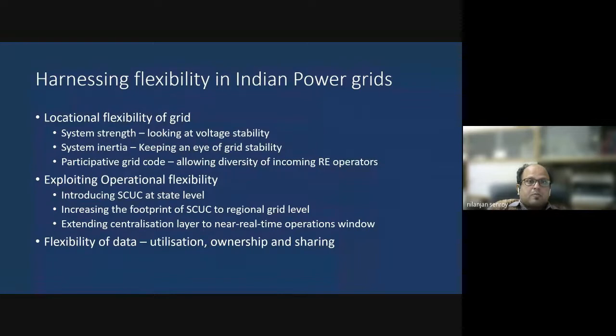Then at important nodes, we need to specify the minimum fault current levels that the grid will provide. And the fault current levels over the years at these nodes must be monitored. And if you find that the fault current levels are going down, then you need to install some equipment there in order to restore the fault current levels back to acceptable levels. So for instance, one very key source of fault current is the synchronous condenser that can help restore fault current levels back. Also remember that grid forming converters, today a lot of people are talking about grid forming converters, can also contribute to system fault current levels.